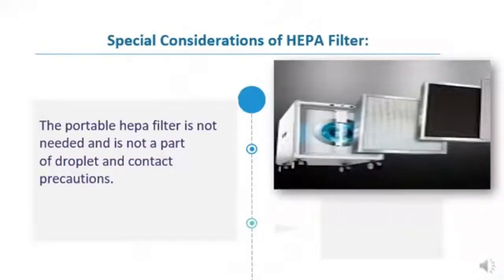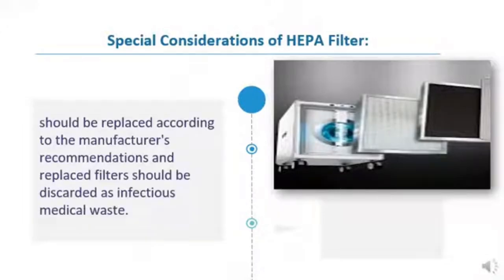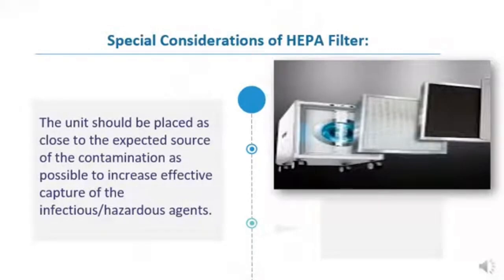We have to consider special considerations for the HEPA filter. The portable HEPA filter is not needed and is not part of droplet and contact precaution requirements. We also have to consider regular replacement of the HEPA filter: replacement should take place according to the manufacturer's instructions or recommendations, and the replaced filter should be discarded immediately as infectious medical waste per policy and procedure. To increase the effectiveness of this machine, we need to place it as close as possible to the expected source of contamination.